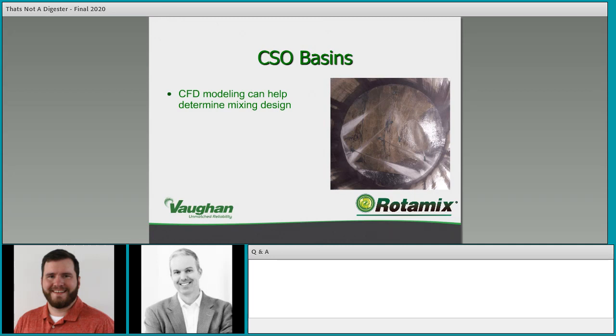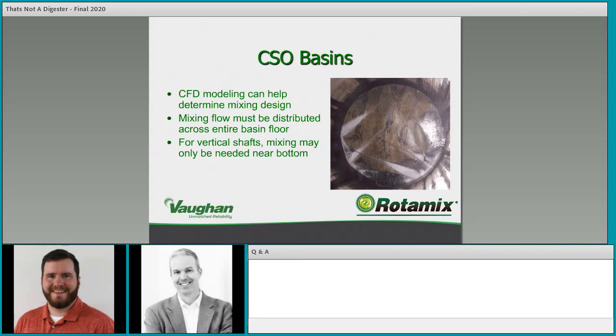Mixing flow must be distributed across the entire basin floor. For vertical shafts, mixing really only needs to be near the bottom in most cases. The picture on the right shows a large CSO tunnel about 100 feet deep — at the bottom you can see a mixing system washing the floor into a small pump pit with dewatering pumps. Everything is being washed into that corner where the pumps can get at it, cleaning the basin on each cycle.